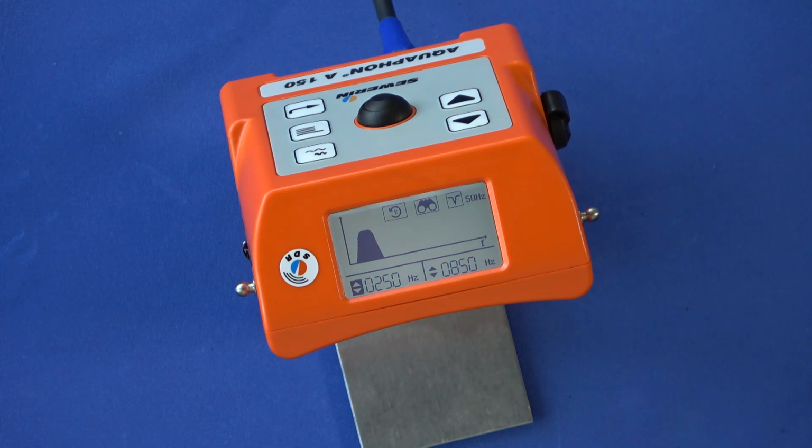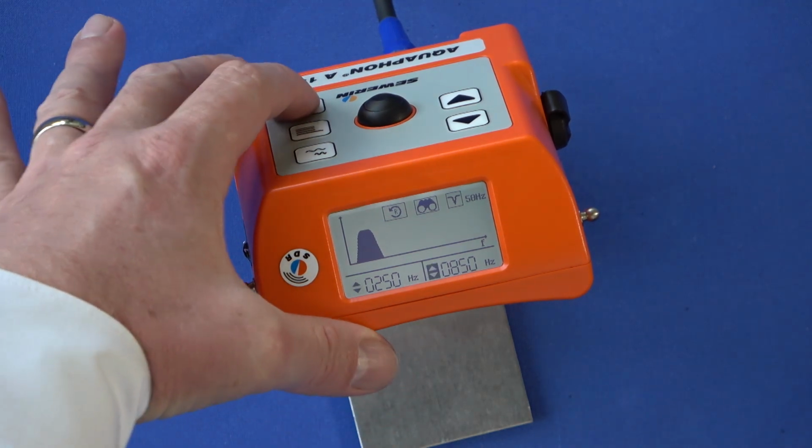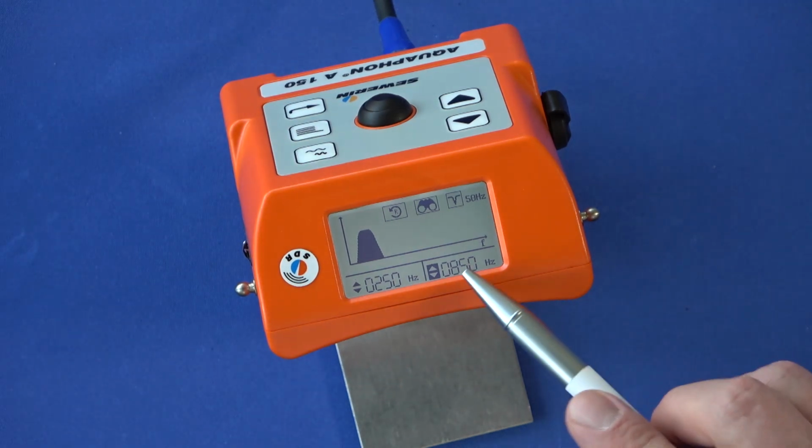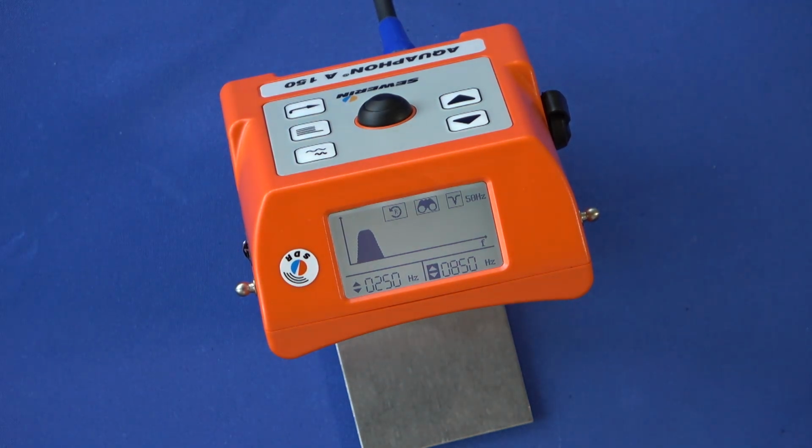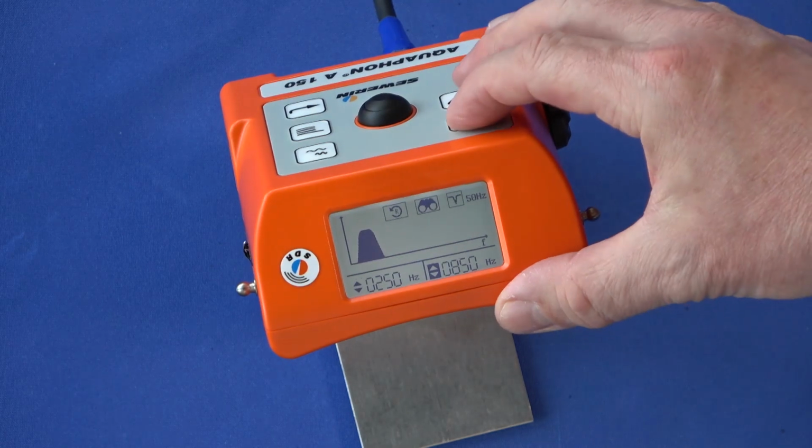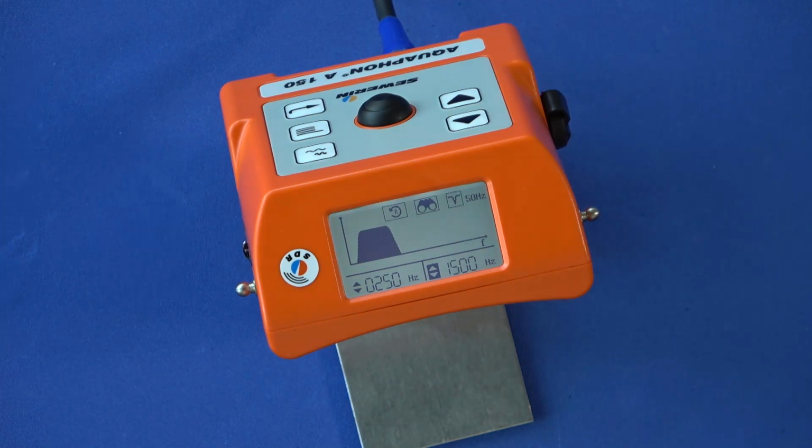If you press the Enter key again, you will reach the setting of the upper filter limit. You can also set these using the arrow keys. The headphones are permanently active during the selection of filters in order to have an immediate feedback. Frequencies from 0 to 2000 Hz are ideal for pre-locating with a test rod. Filter areas up to 850 Hz are often successful for localization with a ground microphone.